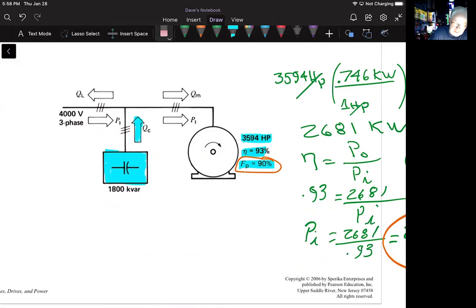So we know that reactors or inductors, as we commonly call them, are loads for reactive power. And that's given to us here, right? And so the reactive power supplied to the motor. We already talked about the active power supplied to the motor. This is reactive power supplied back by the capacitor bank, but this looks like the whole line reactive power is predominantly capacitive. So let's see how that happens. See if you can follow this with me and understand.